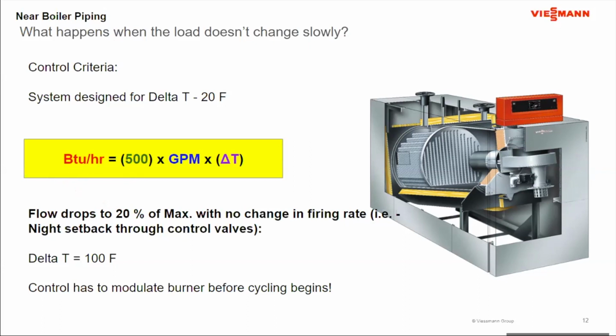What's going to change is the flow rate. So if I drop the flow rate, since the flow rate times the delta T has to add up to the same BTU input, for whatever percentage I change the flow rate, the delta T has to change in the opposite direction by an equal amount. So if the flow rate drops by a factor of 5, the delta T has to increase by a factor of 5.